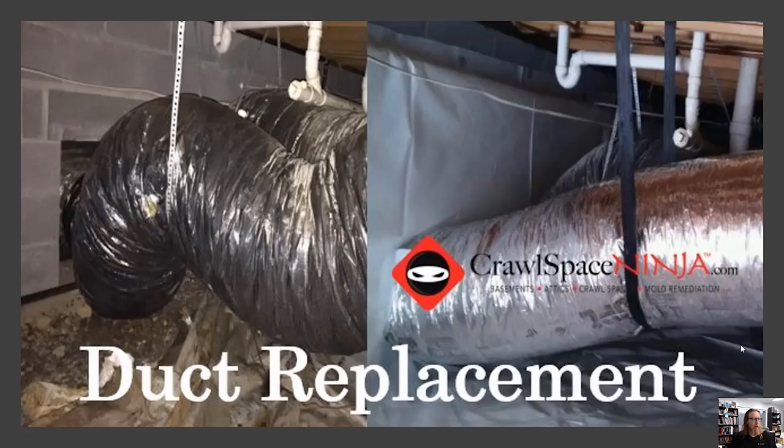I'm going to show you right here what that looks like. This is a project we had done — a little cleaner cut than yours, Josh, but still the same thing. They put a header across right here, and this duct wasn't moving a lot of good air, so we wound up putting foam board in and then straightening the ductwork so that there's better airflow. You can see the foam board raised up off the wall all the way down, and then we taped and sealed around the ductwork itself. For any intrusion points like that, you can use foam board or a combination of mesh, metal, or sheet metal if you're good at that. Wood is good if you're comfortable cutting circular openings, but for us, foam board is just the easiest way to do it.